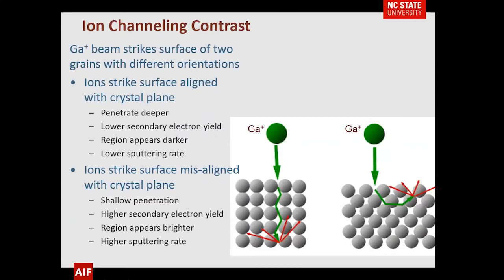Ion channeling contrast is a very useful feature with a FIB. Imagine your gallium beam striking the surface of two grains with different crystalline orientations. On the left, the gallium beam is aligned with the particular atoms — the secondary electrons that come off are from somewhat deeper in the material. On the right, the gallium beam hits a misaligned crystal plane, and secondary electrons are closer to the surface.